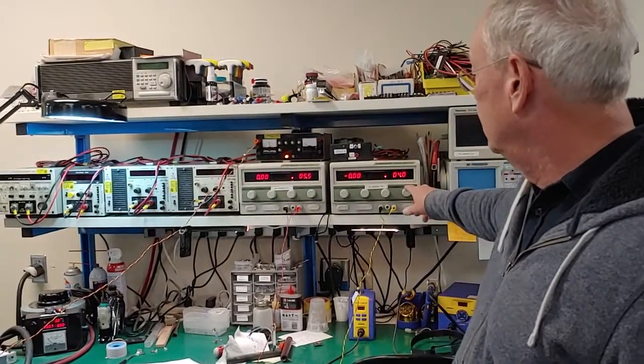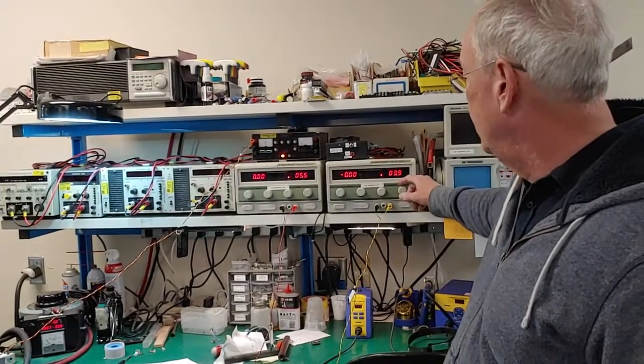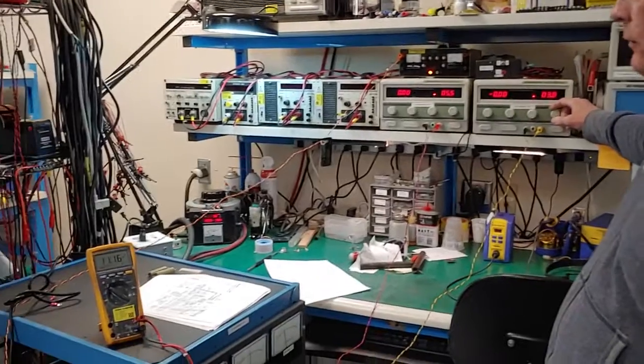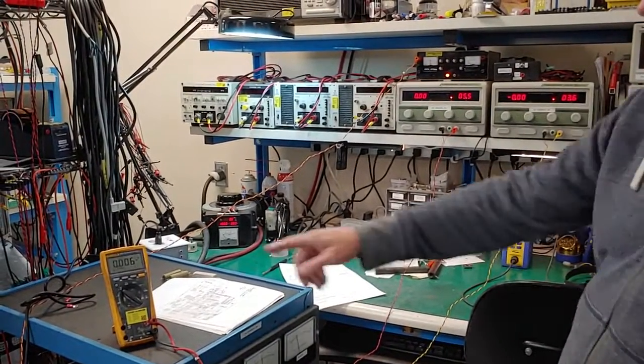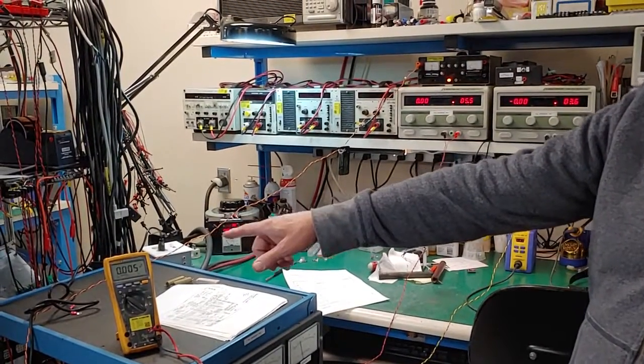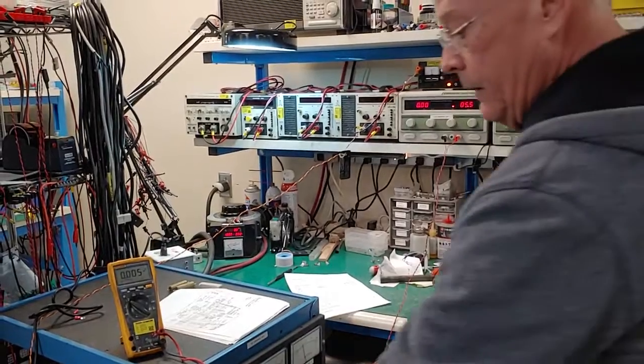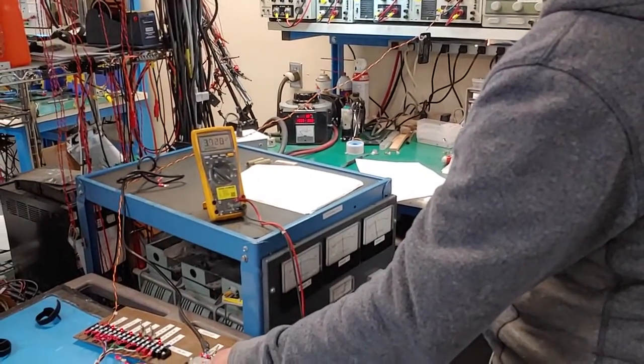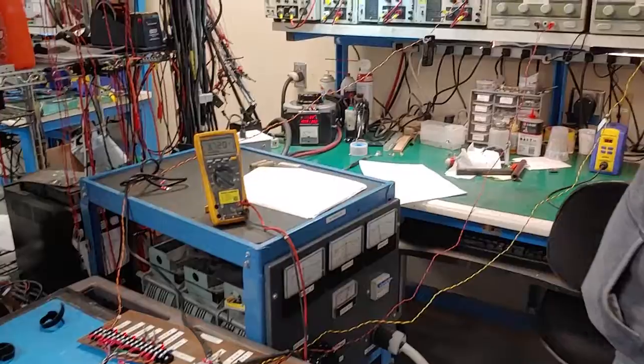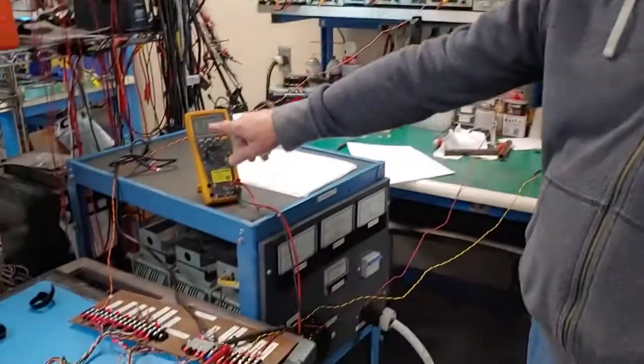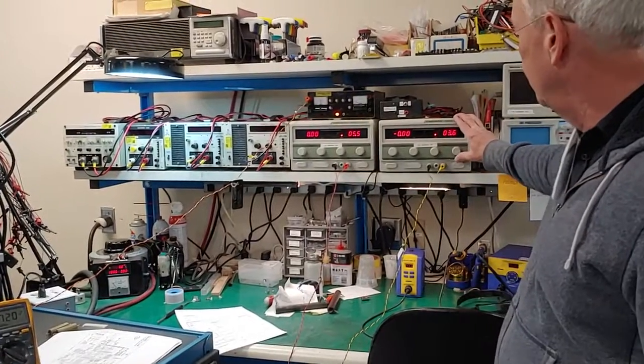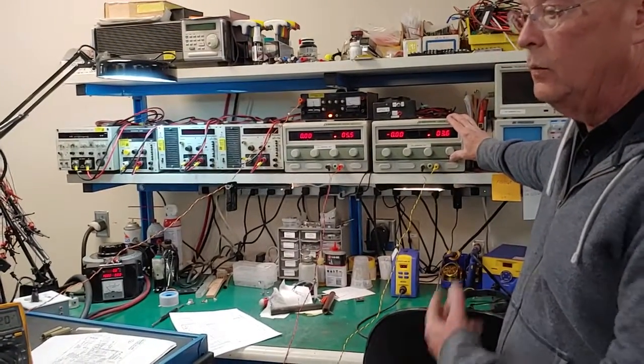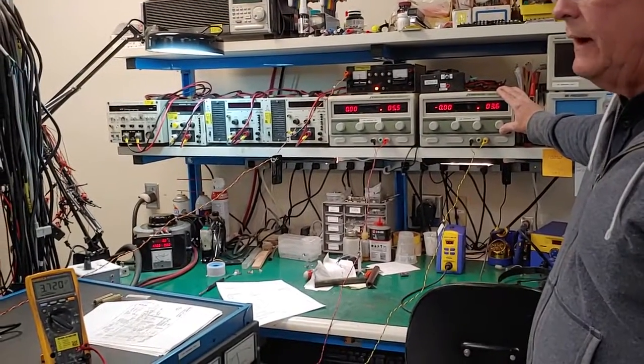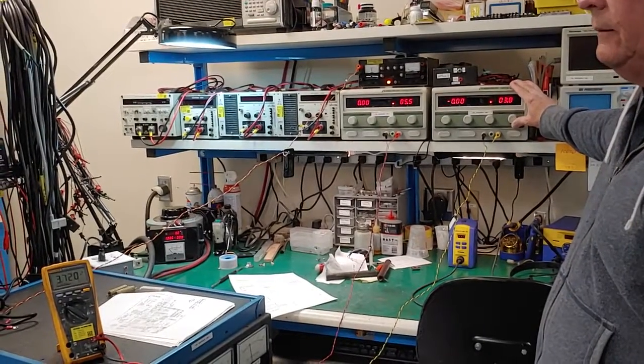Again, I can check the hysteresis of the control loop. I'll bring the control loop below 3.7. As soon as I do, the voltage to the filaments drops clean off. You should see that that point of changeover is very, very close to the actual current. 37.2 milliamps. I'm asking for 36 point, God knows what. That meter's not particularly accurate.